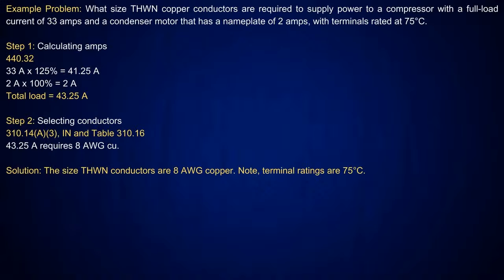So just remember, the first set we did was the motors, where we use the table values. Now, some will say, well, why would I do that? Let's address that right now. Because this is a listed appliance. In other words, it's a unit. It's an assembly. It's all been put together, and they know what's there. That's why you're using the nameplate amperage. Whereas I was doing individual motors, that's not part of an assembly where they put different motors in and created an assembly, in this case an AC unit.